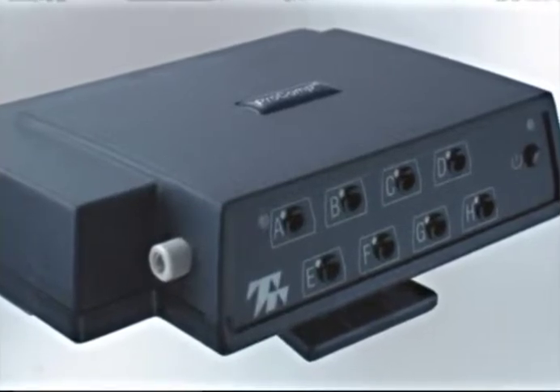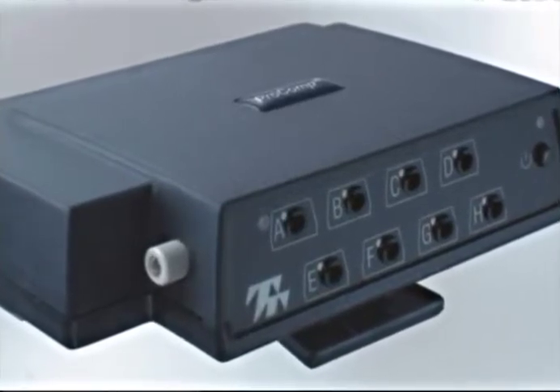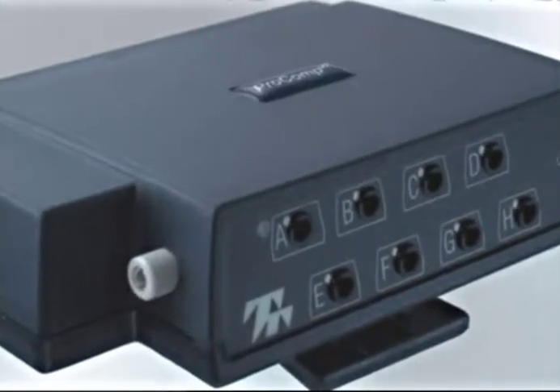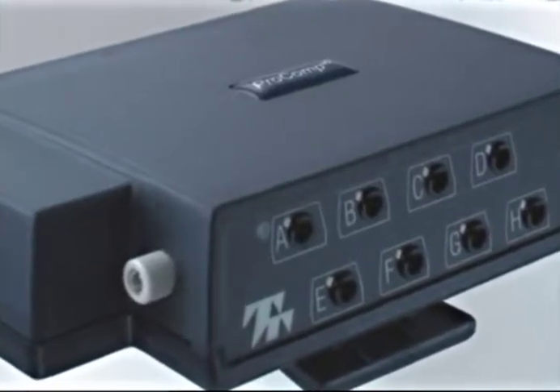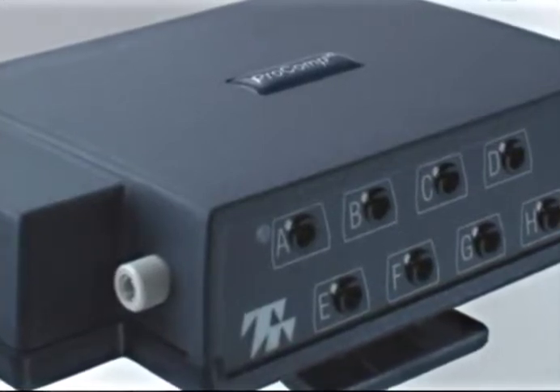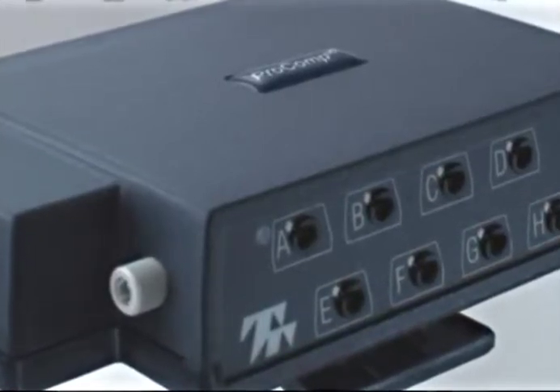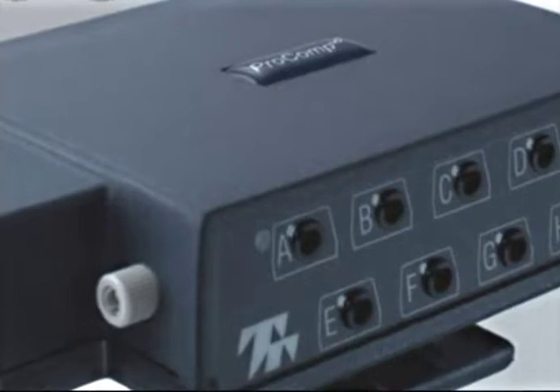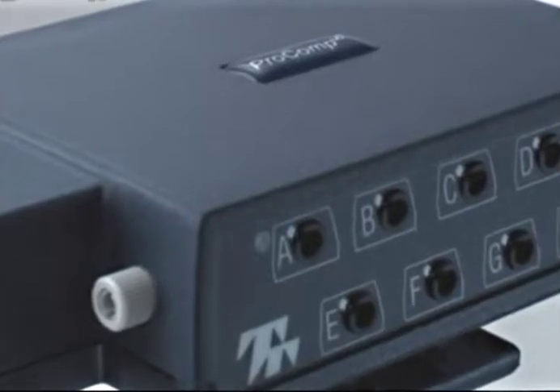The Procomp Infinity is an 8-channel system with the first 2 inputs sampling at 2048 samples per second. These 2 high-speed channels allow for full signal fidelity for viewing heart rate, blood volume, pulse, EKG, and SEMG in raw, median frequency, or spectral analysis formats. The remaining 6 inputs sample at 256 samples per second and can take any combination of sensors.